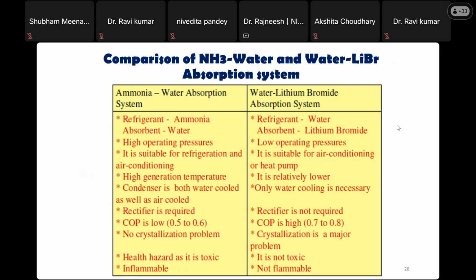The condenser is both water cooled as well as air cooled in aqua ammonia, but in the lithium bromide system only water cooling is required. A rectifier is required in the case of aqua ammonia. The rectifier is used to restrict the carryover problem. As I mentioned, there is a carryover problem: the refrigerant or the desiccant material goes along in the cycle, so it has to be rectified. In the case of water lithium bromide, since water is used as the refrigerant, there is no need of a rectifier. COP in aqua ammonia goes up to 0.6 only, but in water lithium bromide it goes up to 0.8.